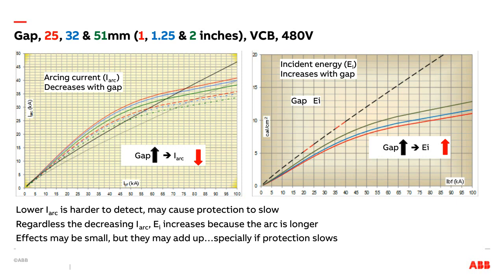And if you go to look at the impact of gap, you'll see that there is a small change in arcing current. There is a small change in energy. And here you'll see the green curves are in the bottom. Here you see the green curves are on the top, which making the gap smaller, conservative. Making the gap larger makes things more difficult. Increases energy, lowers arcing current, makes things more difficult to detect, and makes the energy per unit time higher.